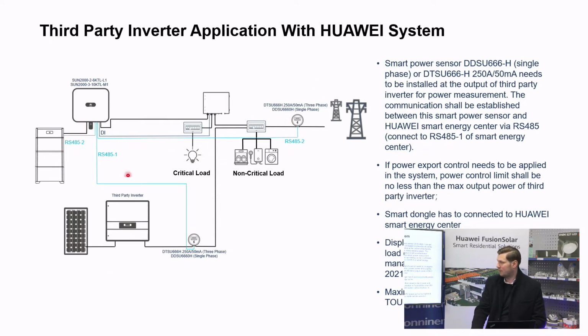So even with a third-party inverter, you can use a scenario like this. If it were a Huawei inverter, like M2, M3 or others, you wouldn't need this power meter, because we'd connect them together with an RS485 cable, and the whole system would work together with only one power meter.